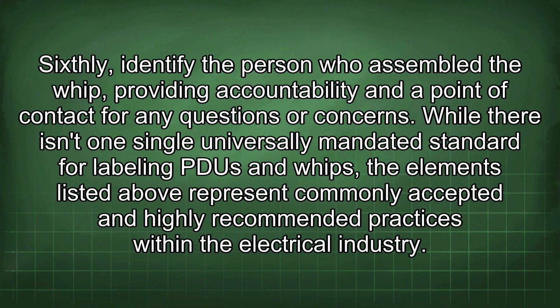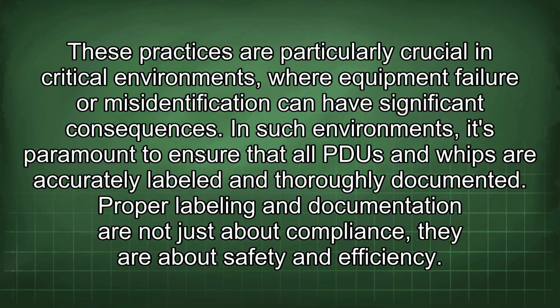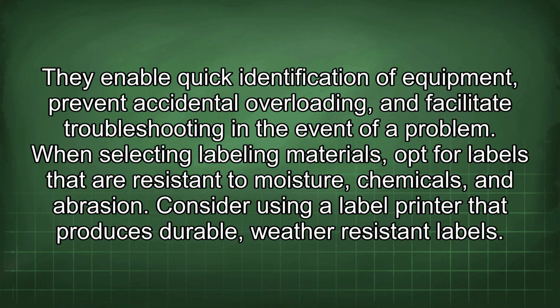While there isn't one single universally mandated standard for labeling PDU and whips, the elements listed above represent commonly accepted and highly recommended practices within the electrical industry. These practices are particularly crucial in critical environments where equipment failure or misidentification can have significant consequences. In such environments, it's paramount to ensure that all PDU and whips are accurately labeled and thoroughly documented. Proper labeling and documentation are not just about compliance, they are about safety and efficiency. They enable quick identification of equipment, prevent accidental overloading, and facilitate troubleshooting in the event of a problem.